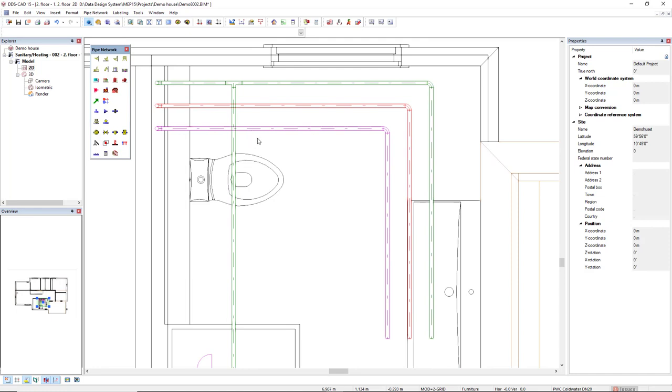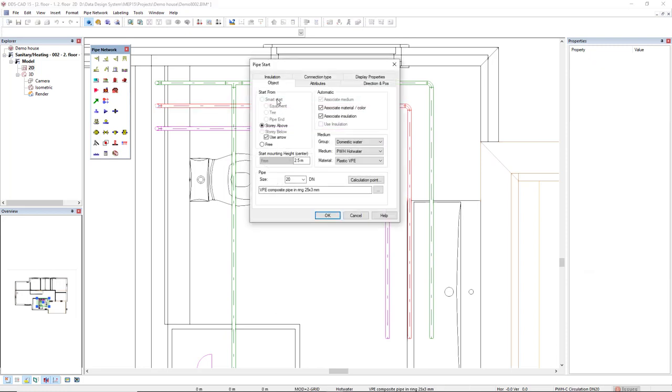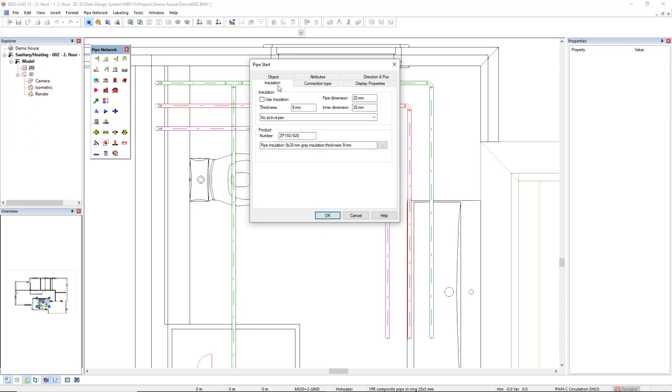All right. I would like to include insulation to this hot water and circulation pipe. What I would do, I would double click this hot water pipe. If I come to the tab Insulation, I can select the checkbox Use Insulation. In the drop-down, in the three dots button, I can access the product database of insulations. This is OK for now. Click OK.